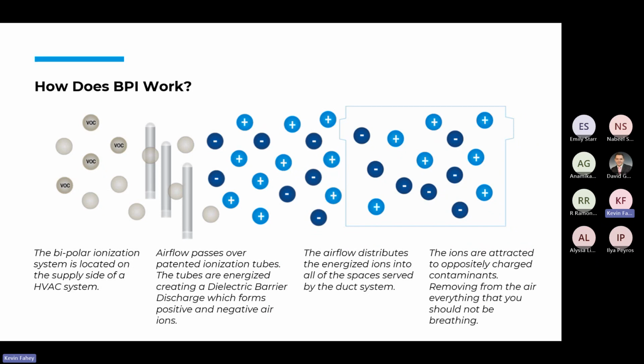And so what we want to do is create these ions with the tubes in the supply air and saturate the occupied environments with these ions so that we're cleaning the contaminants in the space where they're created and generated, not waiting for contaminants to come to the air handler to be cleaned, which is required if you're just using filtration or using UV. The air is being cleaned once it gets to the air handler. So this makes for a more active approach to cleaning your air versus a passive approach of waiting to come to the air handler.